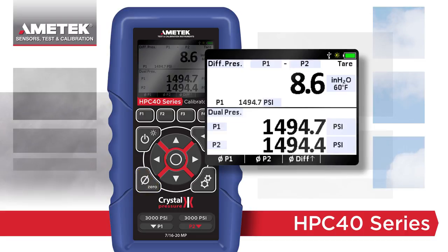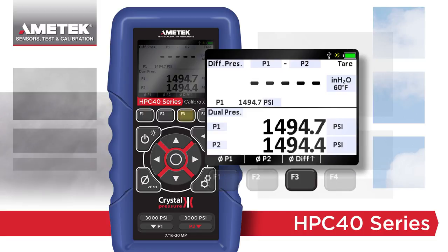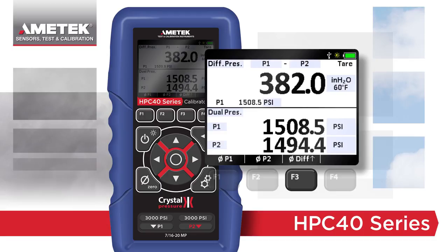In this example, both P1 and P2 are connected to the same pressure. A special Tare DP mode allows you to remove this difference by pressing the differential function button, which increases the accuracy of your DP measurement. Because of the split display, both static pressures can also be viewed at the same time.